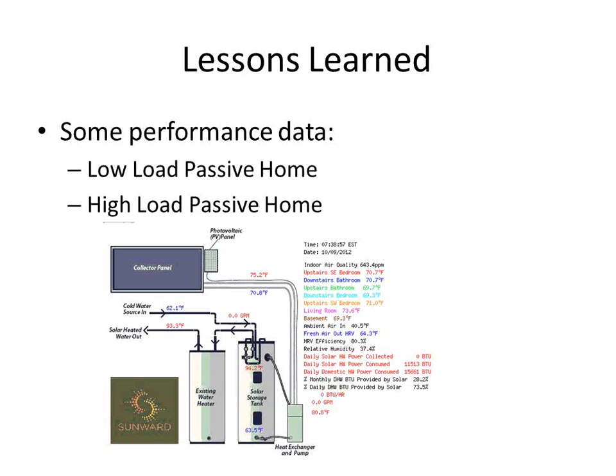This is one of the pages we created for one of the homes - a snapshot I took this morning. It allows us to look at system temperatures in the solar hot water system and calculates how much energy the system is generating, how much of the solar hot water energy you're using on a given day and month, and how much total domestic hot water energy the house is using. So you can calculate what percent of your domestic hot water load is covered by your solar hot water system.